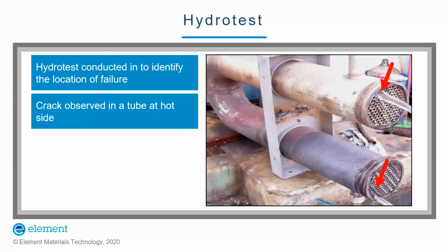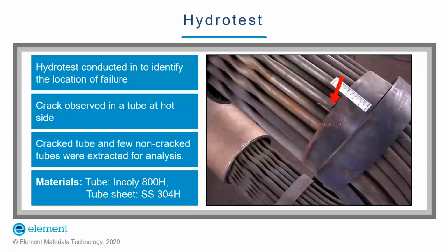Our client delivered the heat exchanger to our facility for a detailed study, and after analyzing the background information and conducting visual examination, it was decided to do a hydro test in order to identify the location of failure. The location of the leak was identified during the hydro test and is indicated in the picture with a red arrow. After the hydro test, the shell of the heat exchanger was cut open and it was observed that one of the tubes cracked at the hot side of the heat exchanger. It was also noted that the crack was very near to the stabilizing strap as shown in the picture.